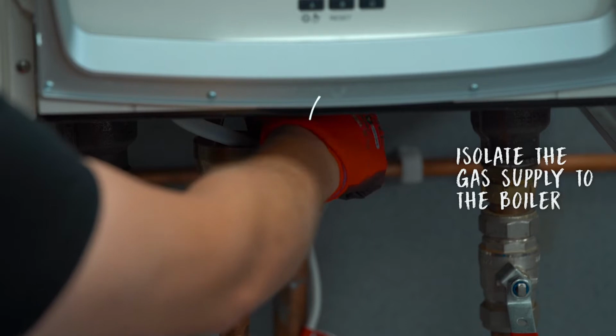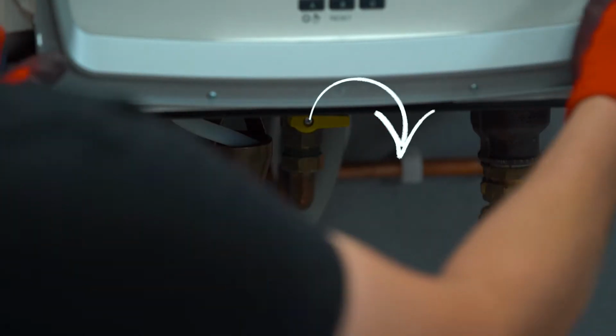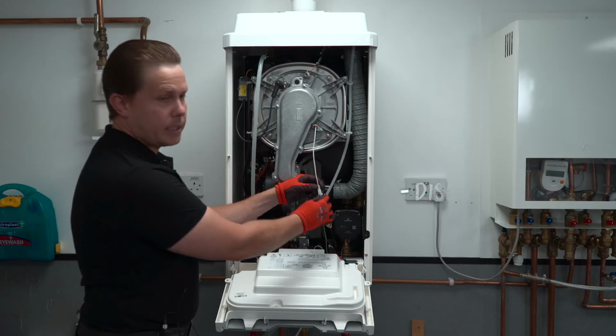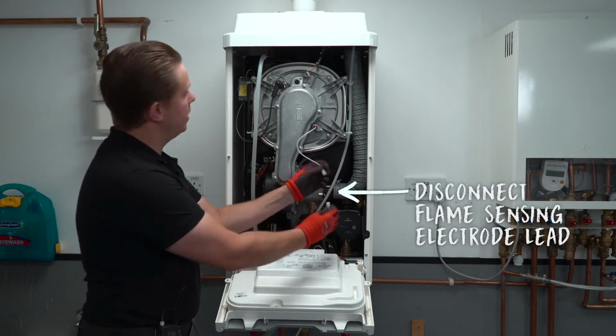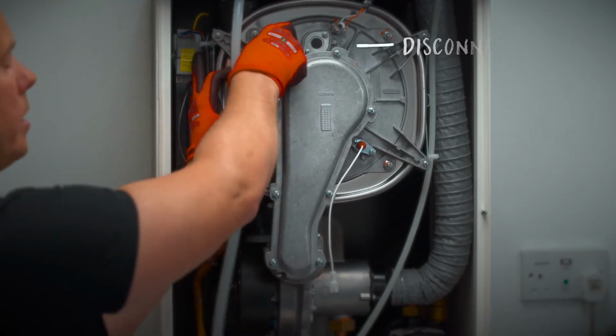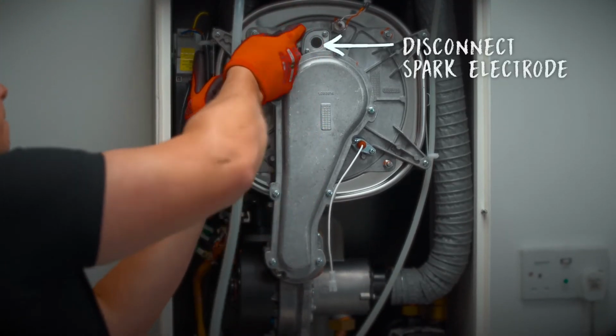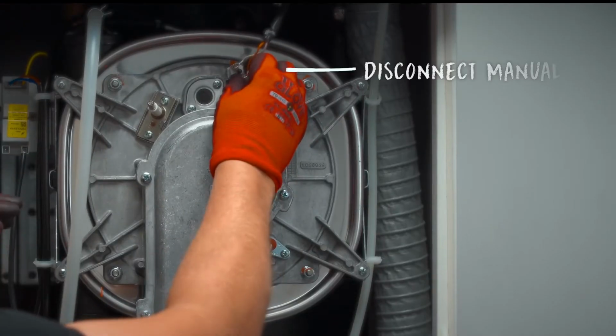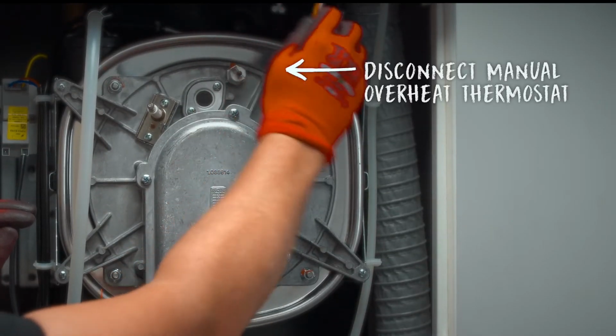Next, isolate the gas supply using the gas isolation valve underneath the boiler. Then disconnect the flame sensing electrode lead, the ignition lead from the spark electrode, and the manual overheat thermostat.